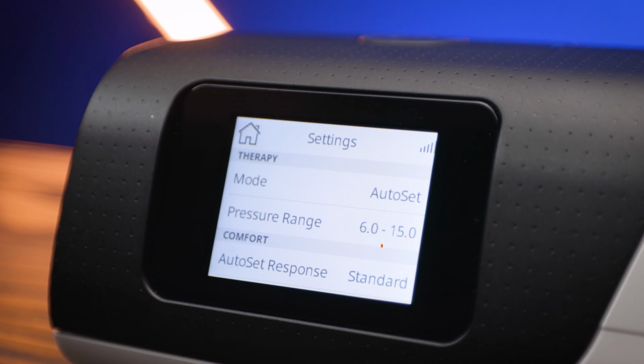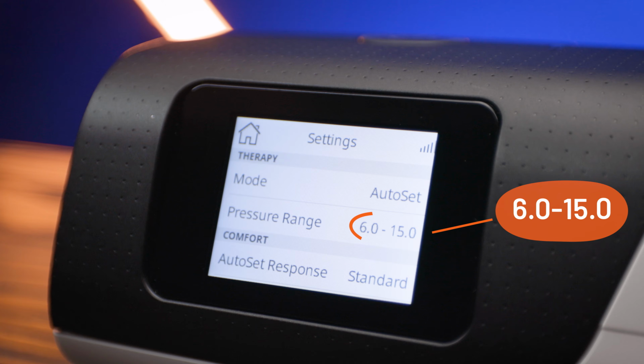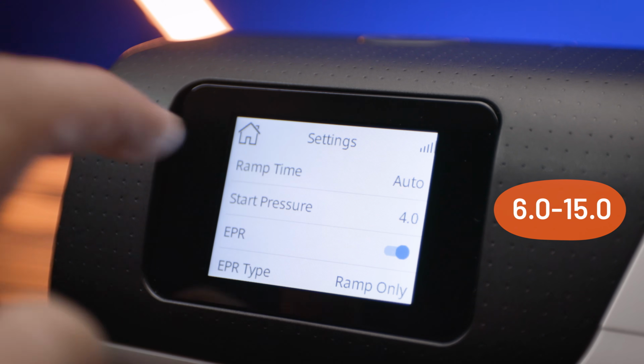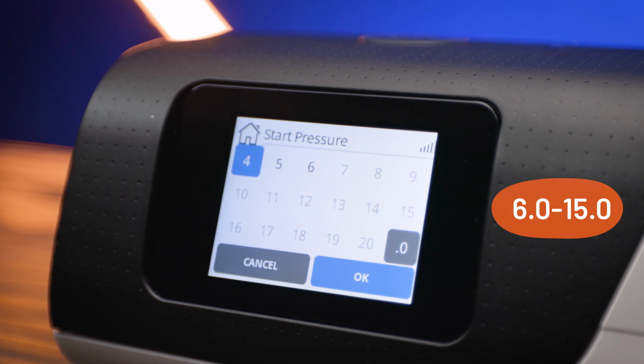If you are using an auto CPAP or APAP device in its auto mode, the starting pressure of the ramp will need to be set below the minimum pressure that has been selected as part of the prescribed pressure range, unless your minimum prescribed pressure is 4, in which case the ramping may match that. How low you make the starting pressure is up to you and should be based on what you find most comfortable. But with most devices, the minimum pressure possible even at the start of the ramp period is 4 cm H2O, which is often referred to on the menu as simply 4.0.